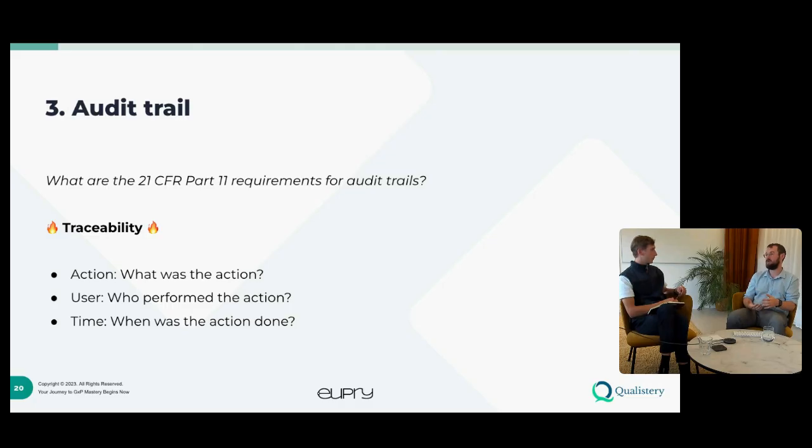Most audit trails can also be filtered by type. So my suggestion will always be to filter by which are the critical changes to a system, and then go through what changes were made and by which people, and whether it makes sense. I've yet to see someone needing to do a report based on the audit trail though, but it's a good question.